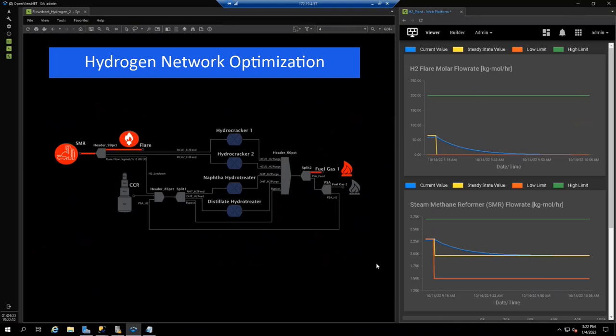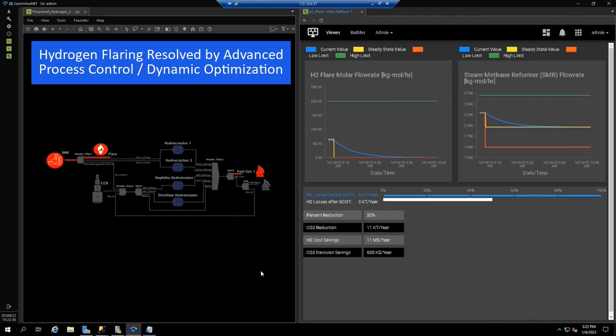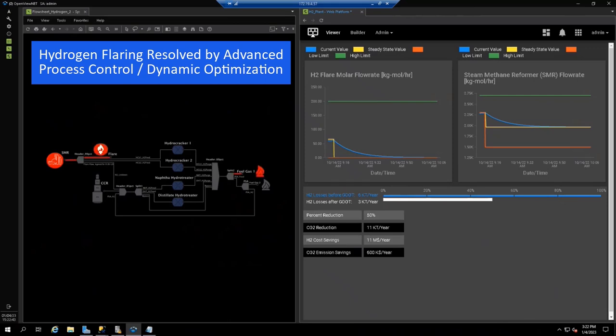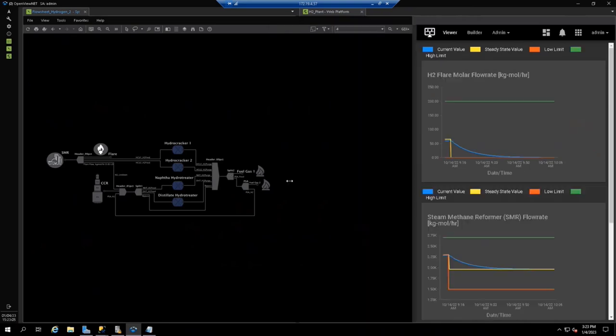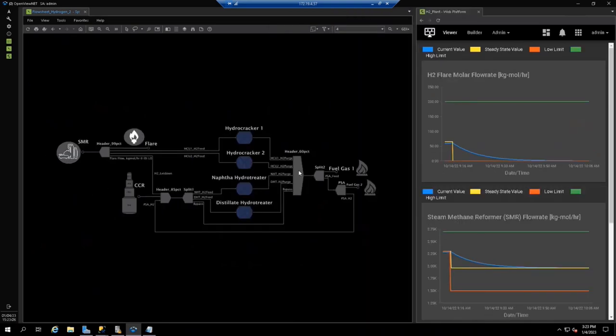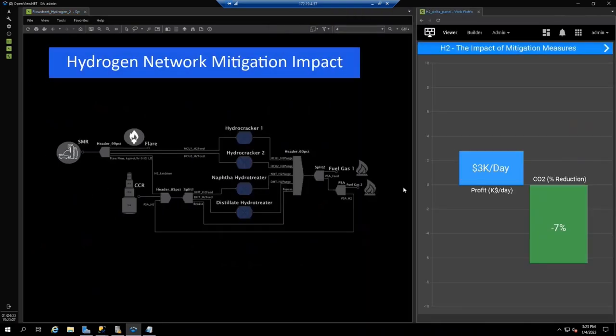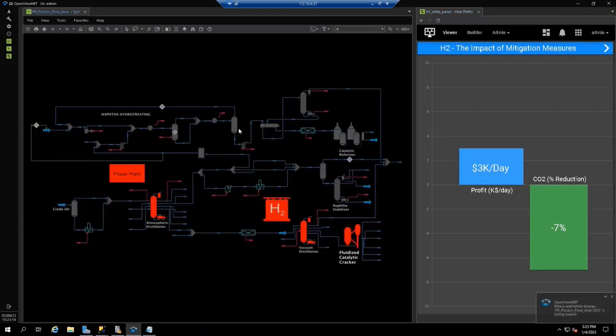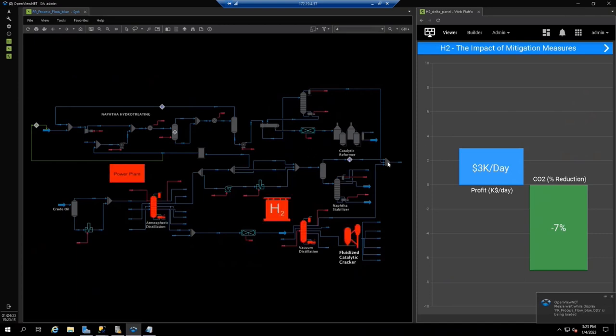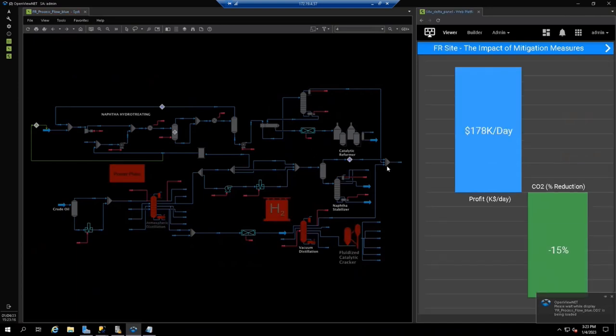This increases hydrogen throughput in the hydrocrackers and hydrotreaters, while decreasing hydrogen production and flaring in the SMR. The optimizer gradually reduces hydrogen flaring to the minimum level. Minimizing hydrogen flaring optimizes production in the SMR. Here you see the hydrogen production in the SMR reduced from 2,300 kgmol per hour to less than 2,000 kgmol. Same as before, the expected hydrogen network mitigation impact can be calculated by running the planning system with these new optimization targets and parameters.